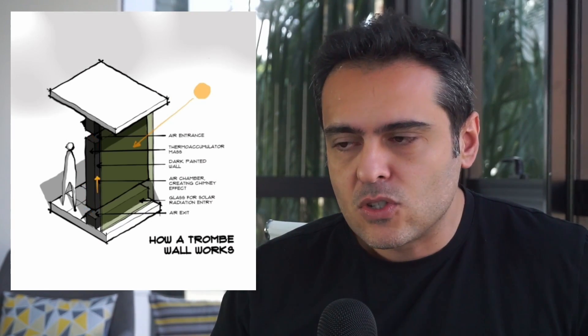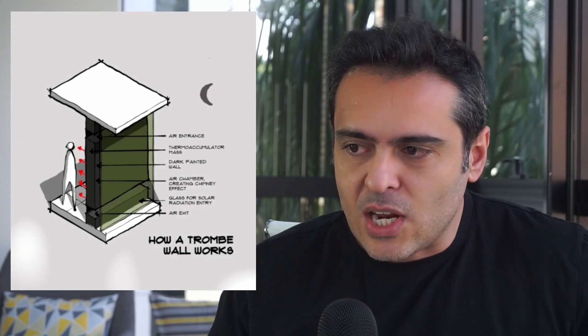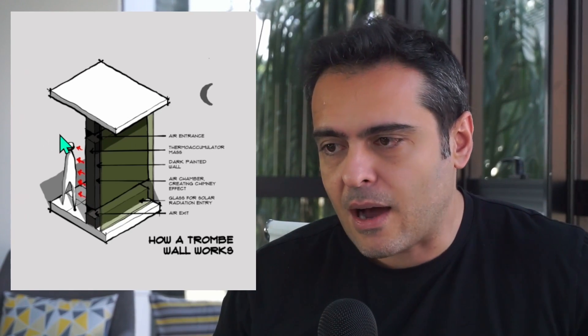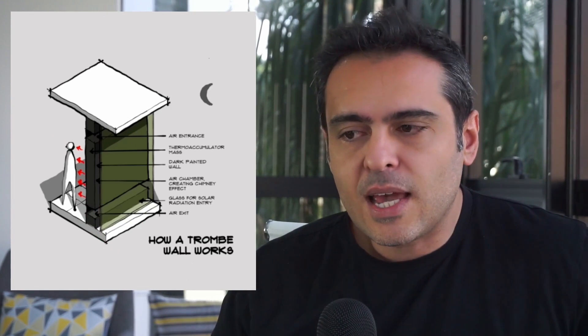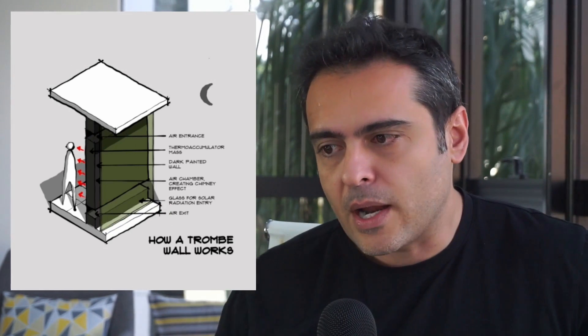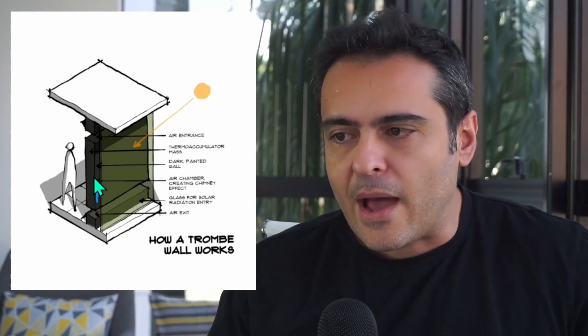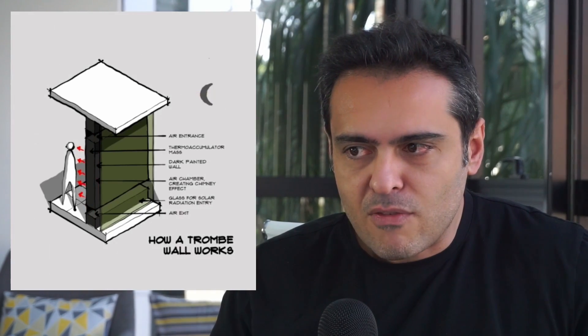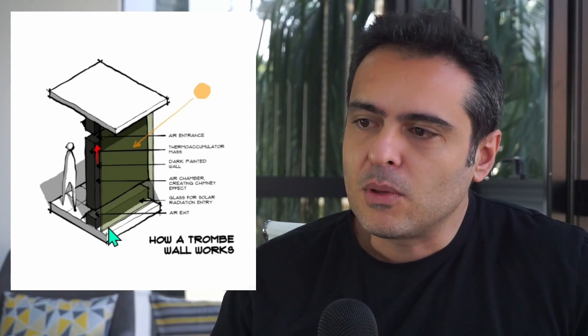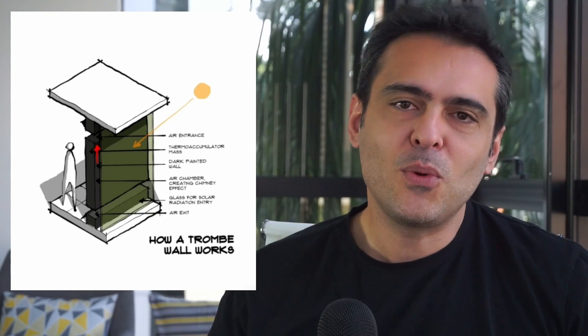And what is this skeleton? You can see that now it's day, so we are having this exchange of temperature. And when it's night, we can have these high-capacity walls to heat our building. Talking about this skeleton: we have the air exit, the air entrance, and here we have the glazing for solar radiation entry. Then we have this air chamber to create the chimney effect. We have this dark painted wall and the thermal accumulator mass. So this is a Trombe wall.